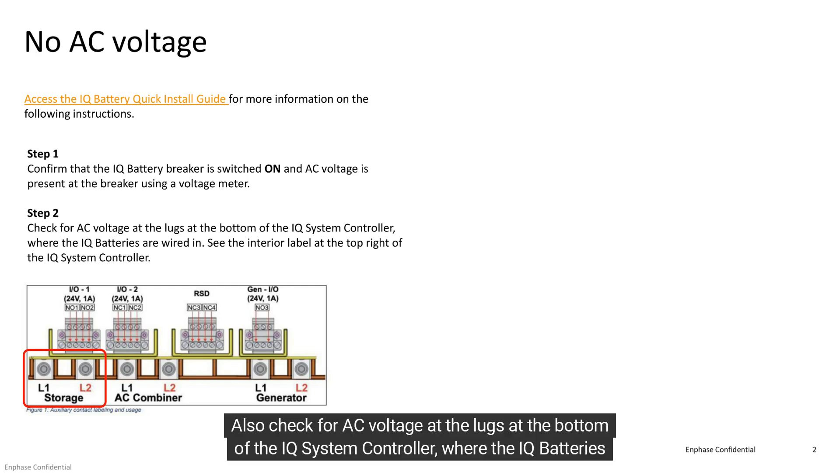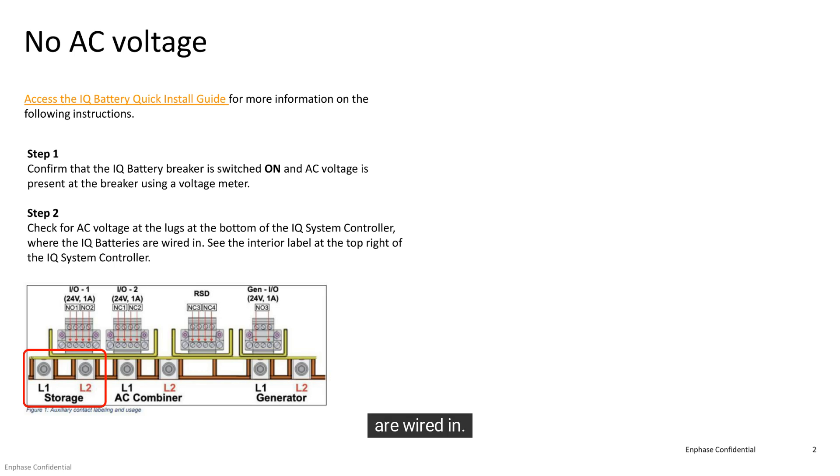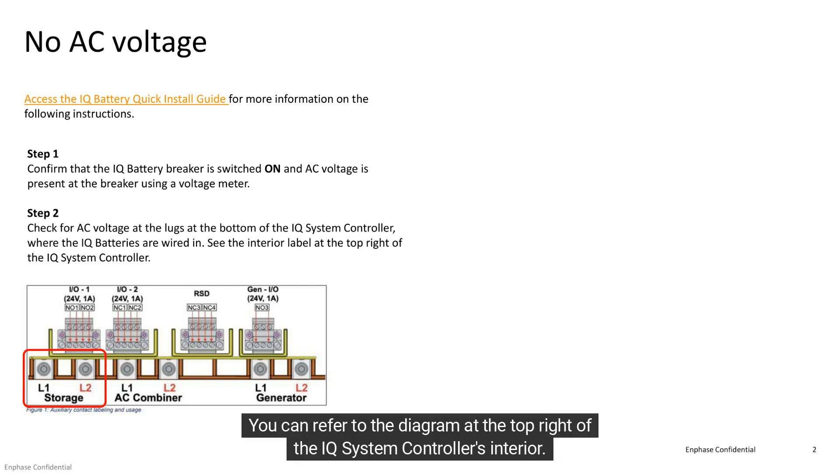Also check for AC voltage at the lugs at the bottom of the IQ System controller, where the IQ batteries are wired in. You can refer to the diagram at the top right of the IQ System controller's interior.